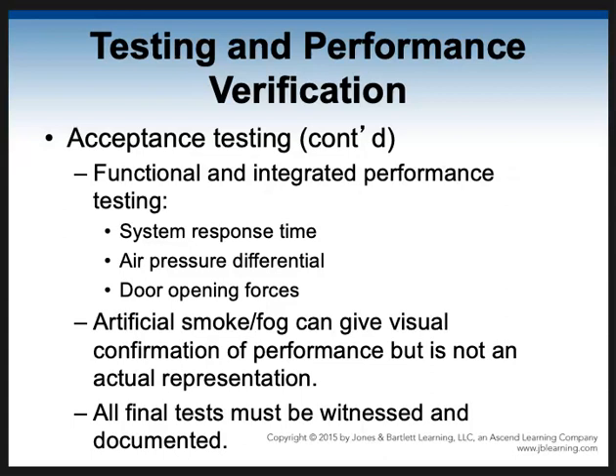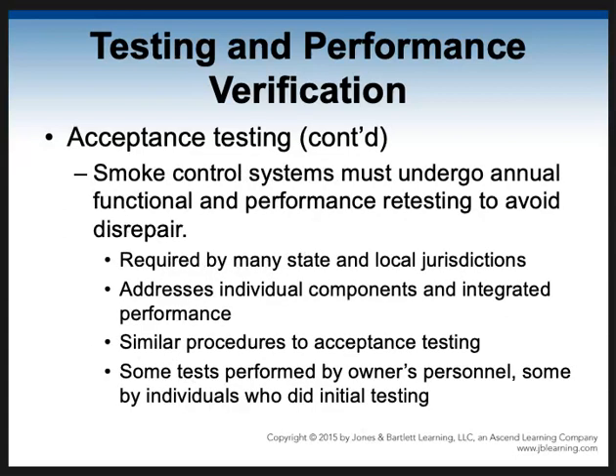So all the tests have to be witnessed by a fire protection inspector and the engineer and the team that installed it. So they not only have to do that to prove that it works when they finish it, but then they have to do annual function and performance testing to avoid disrepair. So they need to make sure that it still works. Generators and these types of systems and then the pumps related to the sprinklers, they're subject to a mechanical failure. They need to be run on a regular basis. The fuel needs to be changed on a regular basis because it gums up. So different states, different local jurisdictions have rules about how often they have to be done.